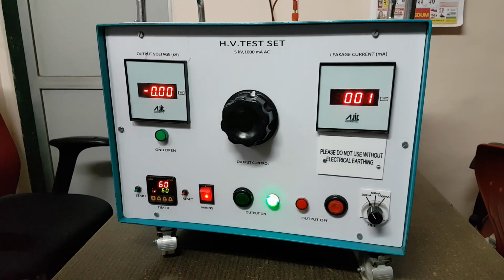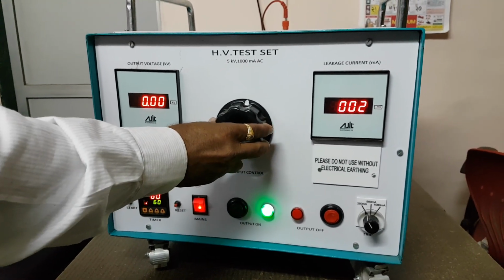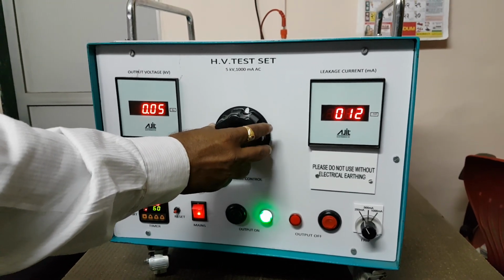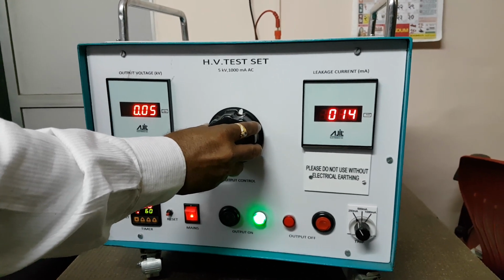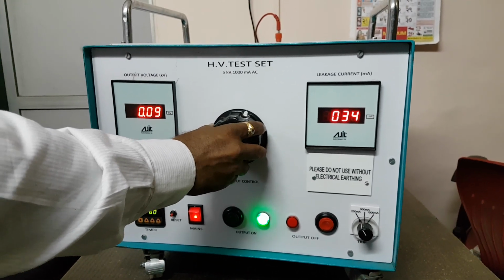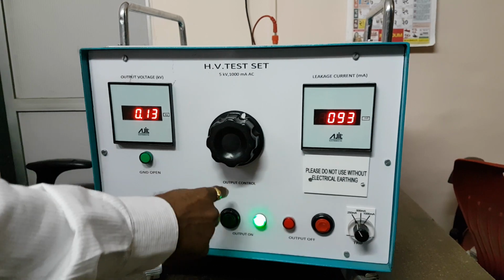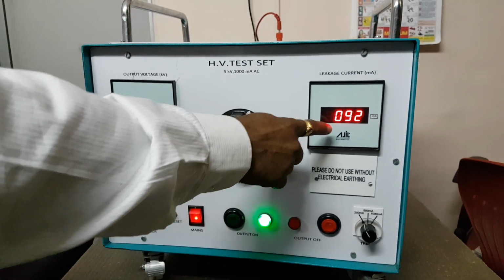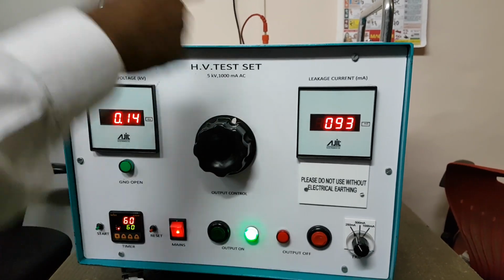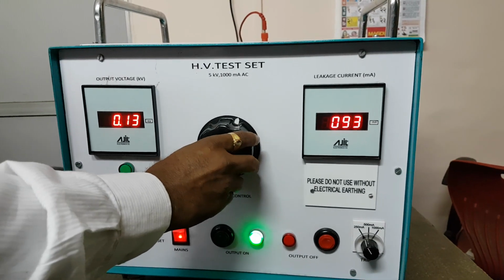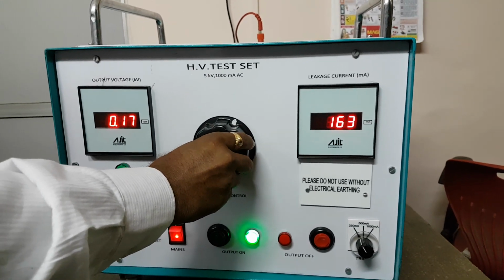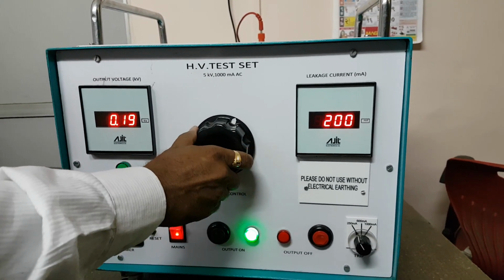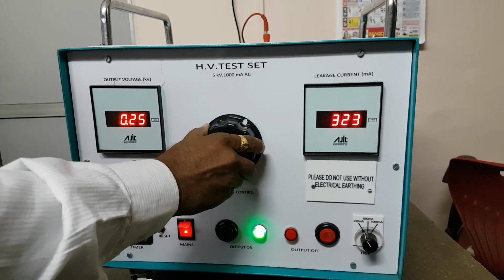So high voltage has been started, and if I give some input to the high voltage transformer by turning this output control knob, we can see a short circuit current is flowing in the output. But if this short circuit current exceeds 250 milliamps, then the instrument trips off.